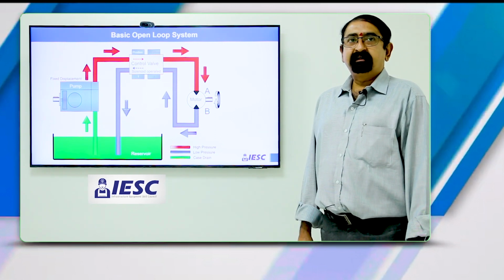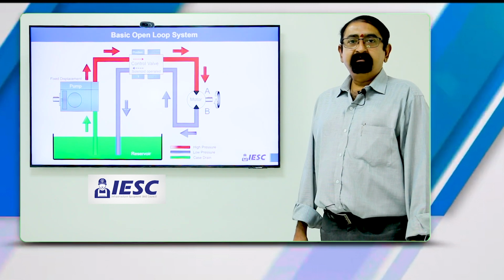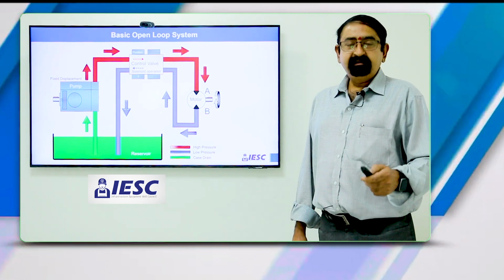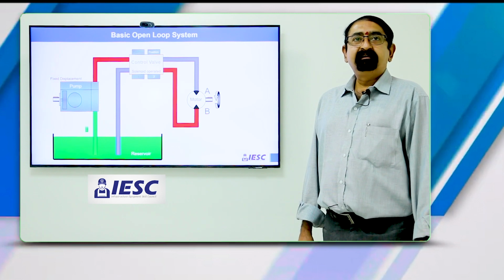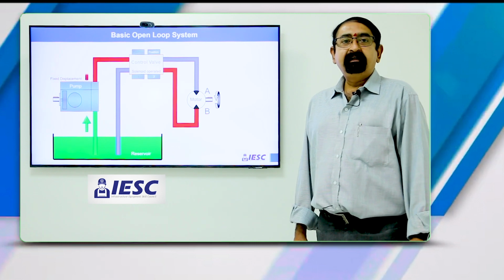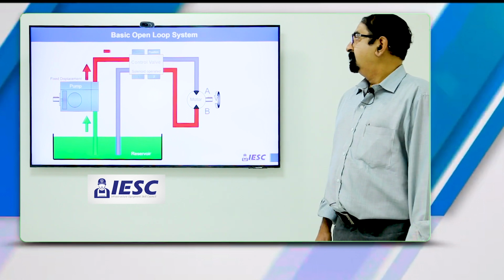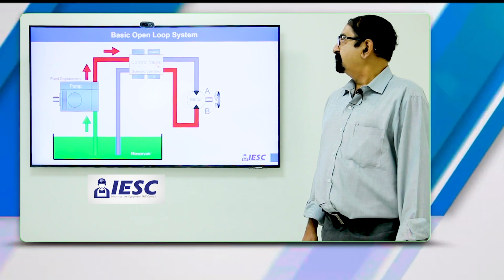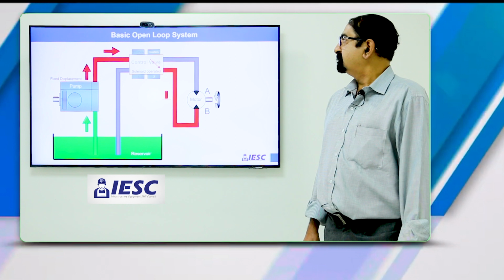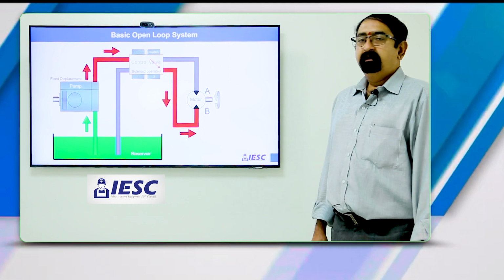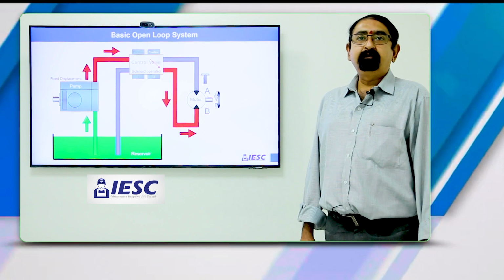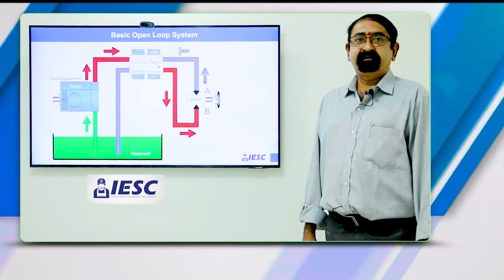This is in one direction, but because it is a bidirectional flow motor, we can change the direction of flow by changing the position of the solenoid, which is usually electrically operated. The oil now comes from the pump as usual, but in the case of the solenoid, the direction is changed, and therefore this causes the oil to move in a different direction, and the motor rotates in the opposite direction.